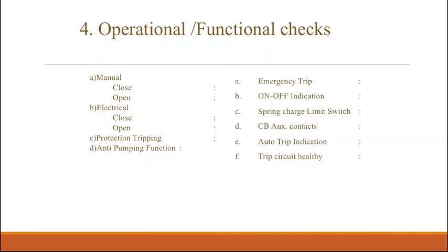Here for the auto recloser function, when I extend the auto recloser closing command, before that I should know the spring ready status. The spring ready status I can get only from the spring charge status. If the spring charge is okay, then only I can give the closing command. For that purpose, the spring charge limit switch I have to check.